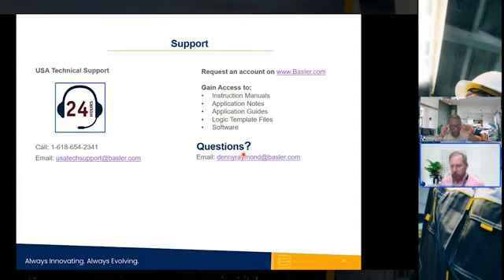Great. A couple more questions. Does the genset need to be shut down and restarted to transition from grid following mode to grid forming mode? No, it does not. All it takes is just changing the status of the parallel to mains logic element, and that takes place within milliseconds. From a control standpoint, it does not. The controller will process that logic very fast within milliseconds and make those adjustments.